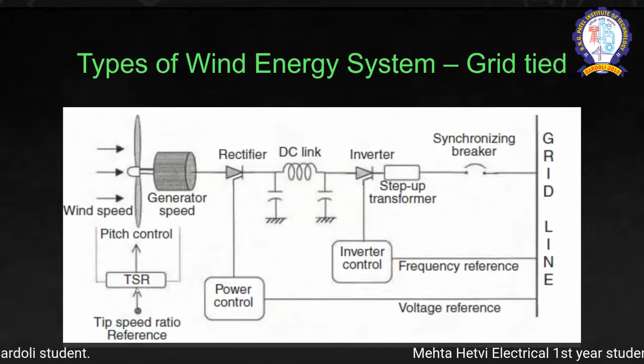In the direct drive system, the generator speed is observed and compared with a tip speed ratio control. The tip speed ratio is the ratio of the speed at the tip of the blade divided by the wind speed. As the wind speed changes, this TSR changes. As this ratio changes, we need to accommodate tip speed ratio control and pitch control to extract maximum mechanical power from the wind turbine.